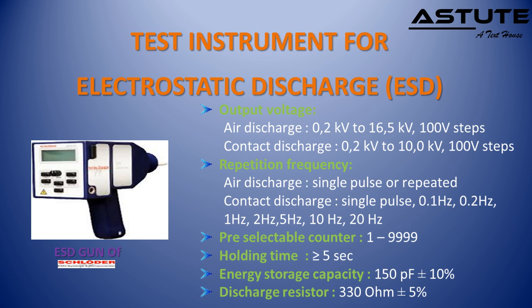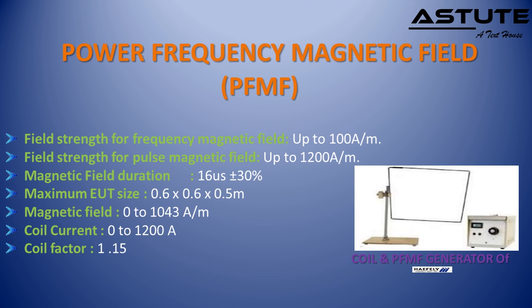For the electrostatic discharge immunity testing of equipment, we use ESD gun of Schloeder with output voltage range of, for air discharges 0.2 kV to 16.5 kV and for contact discharges 0.2 kV to 10.0 kV. Presently we utilize from 2 kV to 8 kV for medical device testing. For power frequency magnetic field immunity testing of equipments, we use PFMF generator and coil of Haefely with field strength up to 100 ampere per meter. 1 meter square loop coil is used to produce required magnetic field in ampere per meter.